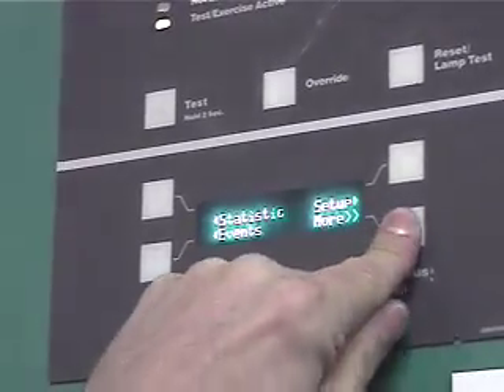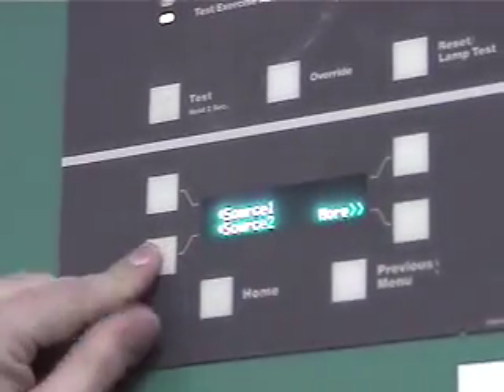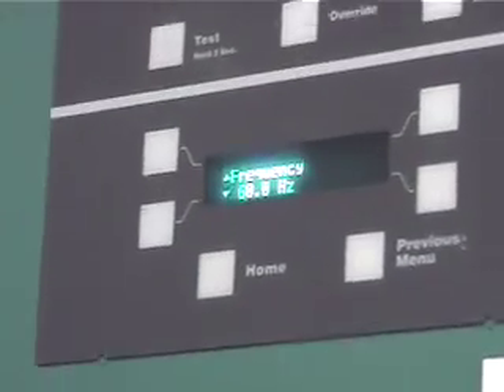But the other thing is our frequency on the generator, I have to change that a little bit. I turn it up to 60.1 hertz. If both of them are exactly 60 hertz, which if you come over here to source one, it's going to be 60.0 hertz.